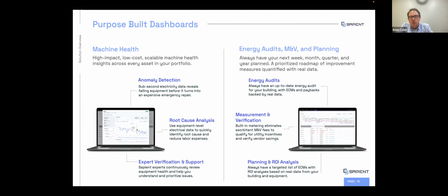From there, we do machine health, so we'll note anything from pieces of equipment that start to fail, things that are causing a higher draw. We've seen pretty significantly that about 70% of the drives we find in the field end up being left in bypass, usually because someone did maintenance and that's where it got left.